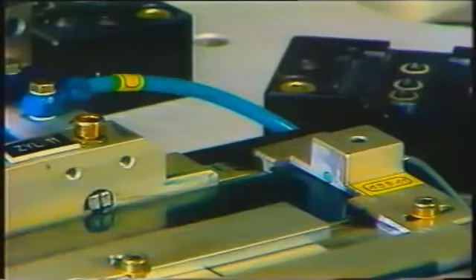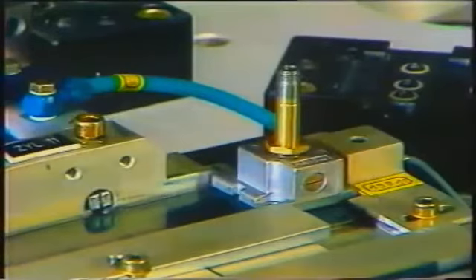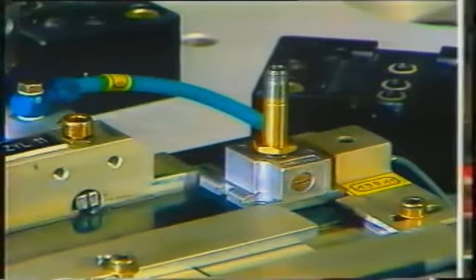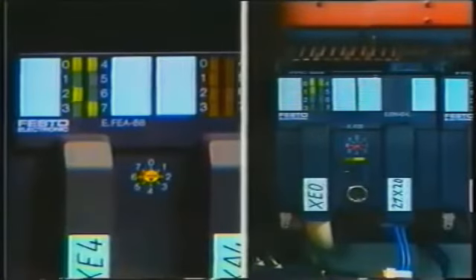Here an example. At the end of a conveyor belt, a proximity switch detects whether a valve is present or not for the next step of the process. If a valve is present, a signal is given to a terminal. This signal is passed via the terminal to the input module. The input module converts this signal so that it can be processed by the central control unit, a small but powerful computer.